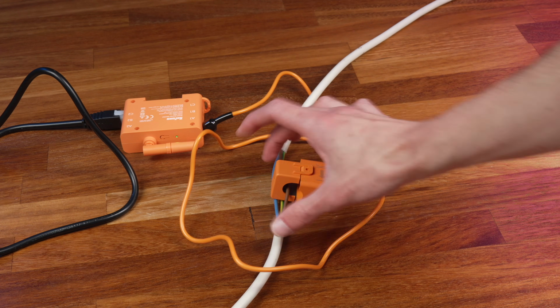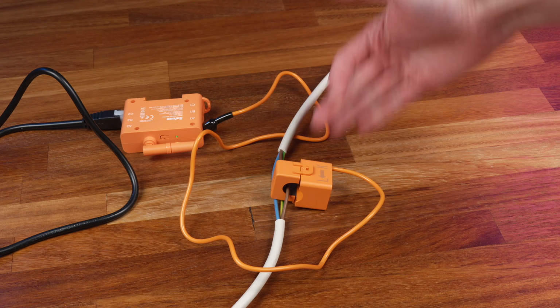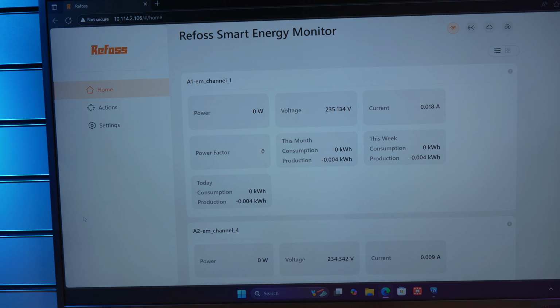So now, let's test it all out. I've clipped the CT around the wire here with the arrow pointing in the direction of current flow towards the socket, and then I've connected the CT into the energy monitor and powered it all up. So now with all that set up, we can see the readings from that port on the screen here, and if we turn on the load, for which I'm just using a hairdryer to test this out, turn on that hairdryer, we'll get a reading.